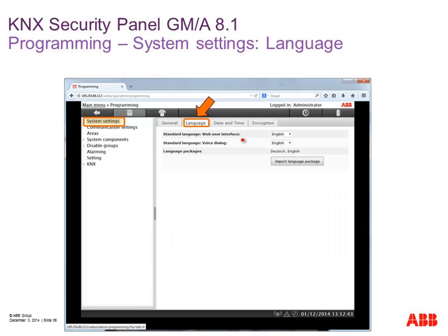In the next window 'language,' we can set the default language of the user interface — so when you open your browser and type the IP address you get the login window in that language, for example English. We can also set the language of the voice dialing machine for sending alarm messages via telephone. The panel is delivered with two languages — German and English. For more languages like Italian or Spanish, you go to our website, download language packages, copy them to an SD card, insert the SD card in the security panel, and import via this button.